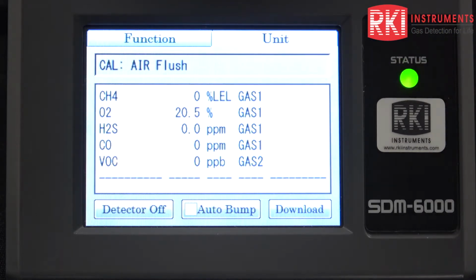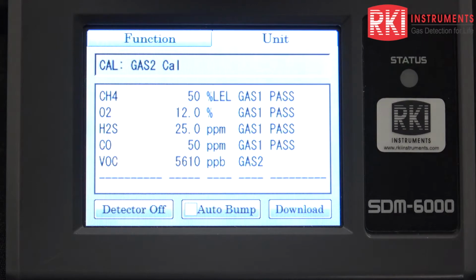You can also go into the unit tab. That way you can see what the sensors are going through right now. So right now it's doing gas 1 cal, as it says on top right there. It's going to do the 4 gas mix first, since that's in gas 1. Those are pretty close to the values of the cylinders, if you're noticing. And it's going to say pass initially, and then it's going to say gas 2 cal, which is the isobutylene. So you're going to see that go up.